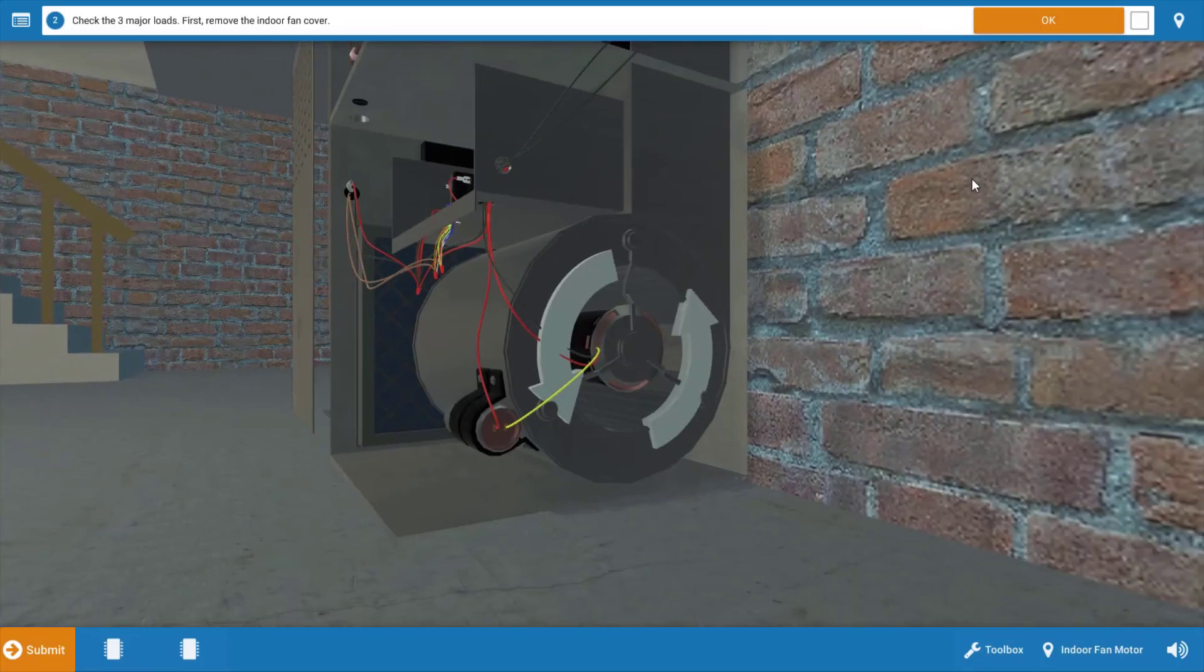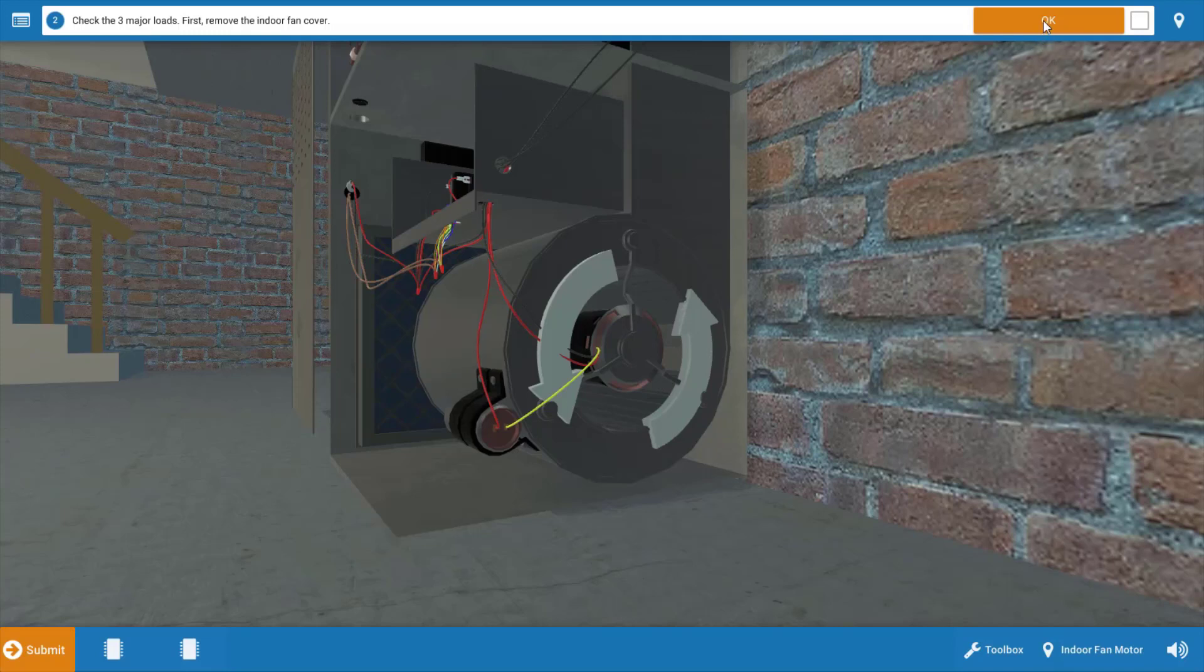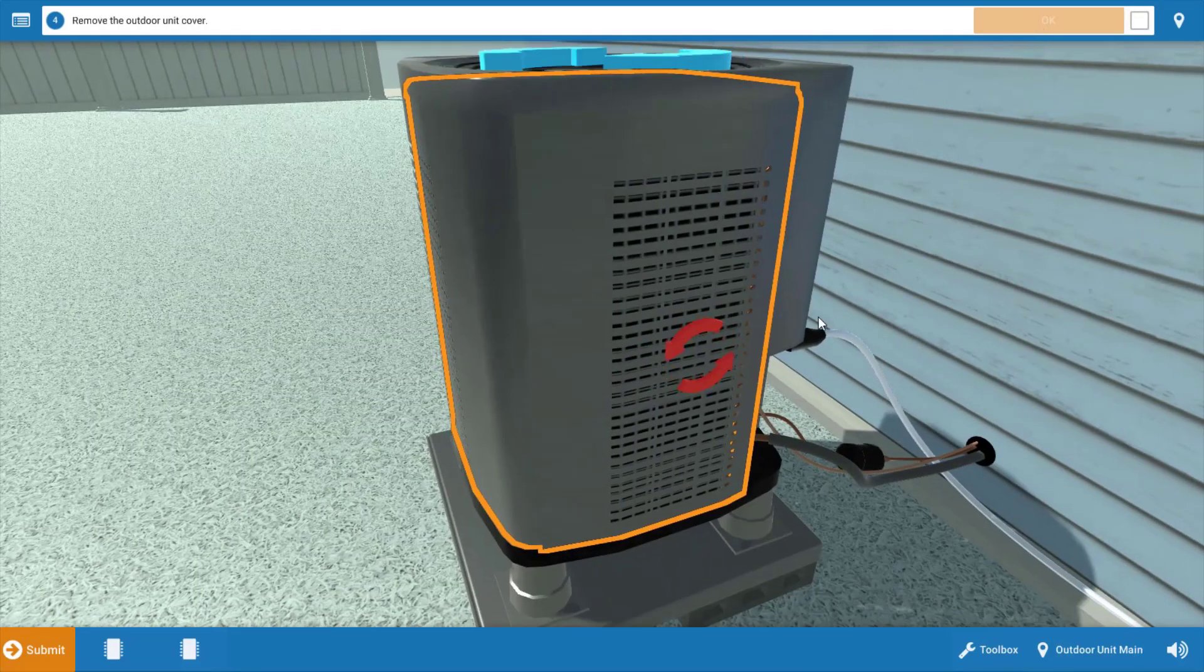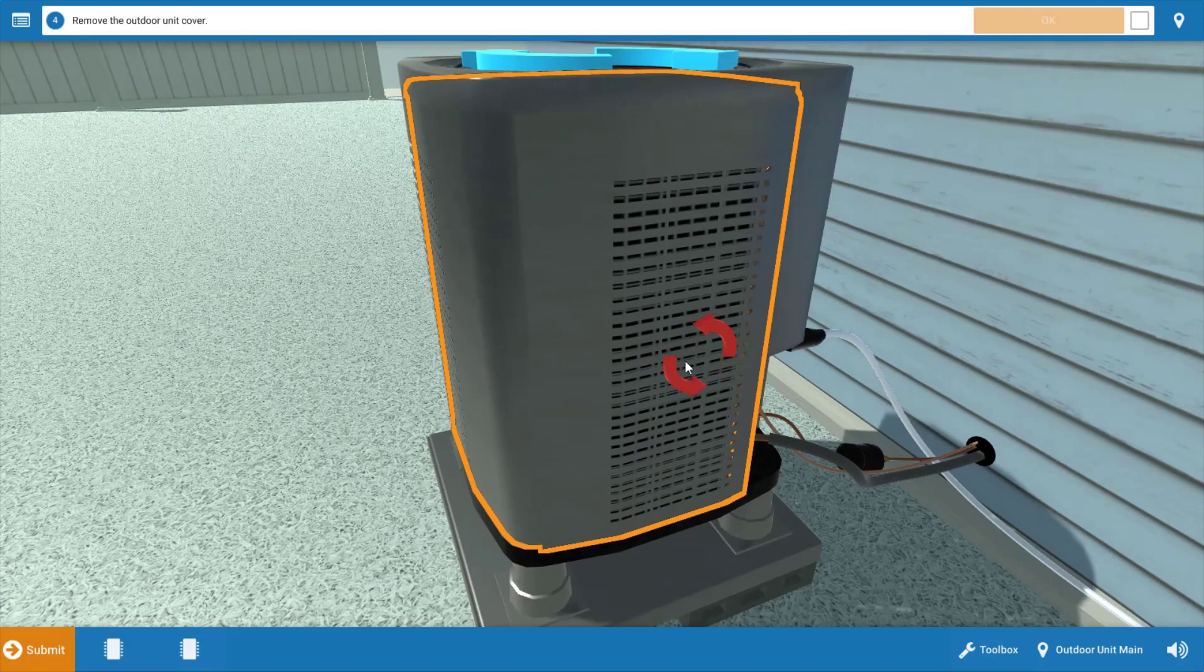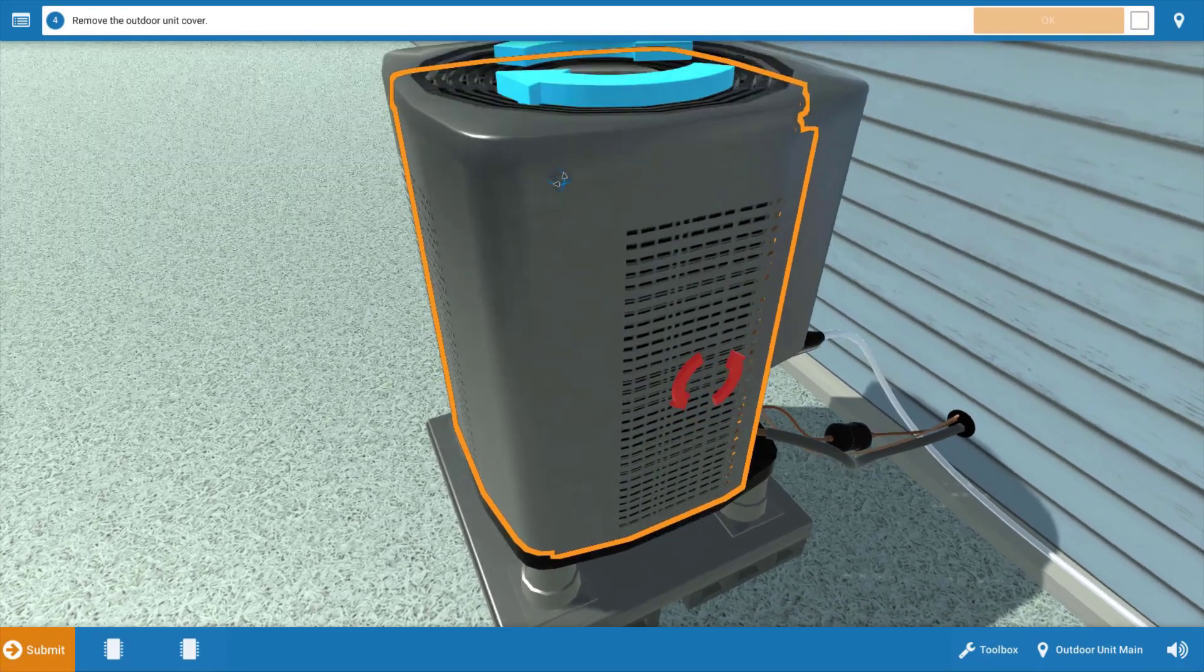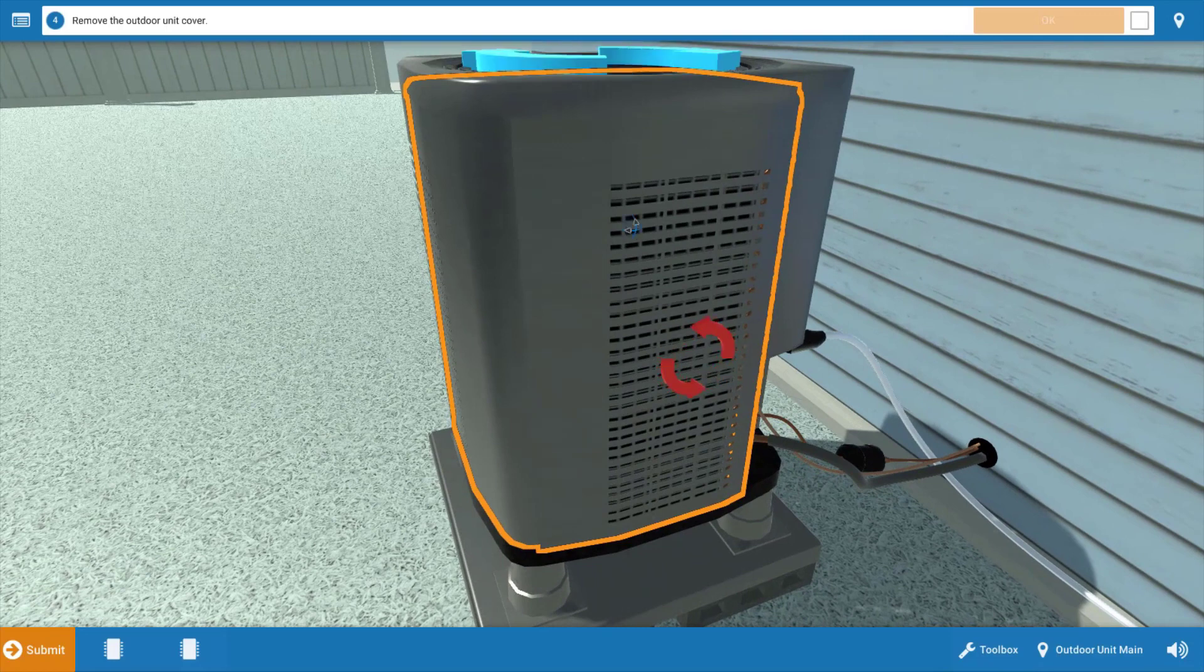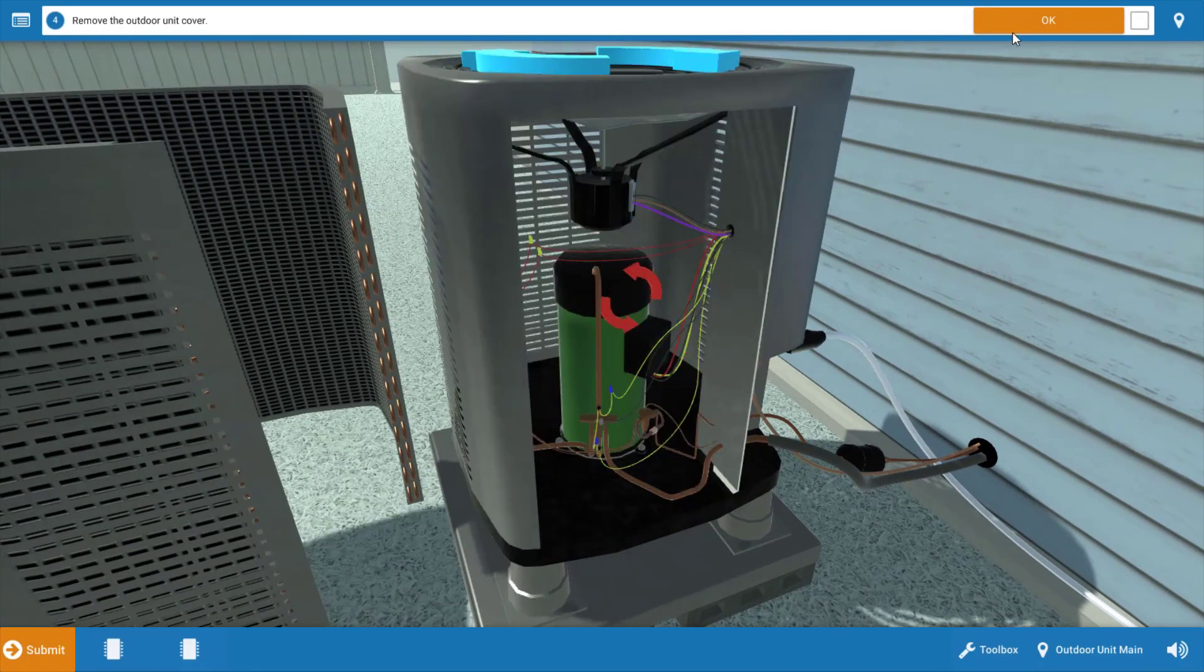Now we need to take a brief inventory of which electrical loads are operating. I've removed the cover here, and we can see that the indoor fan motor is not operating. So once we've removed the cover, we click OK, and we're going to click no that the indoor fan motor is not running.